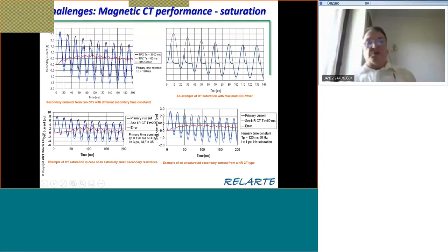And the guy who is developing a relay there, which is installed, for example, even a few hundred meters away from here, and they get such signals from the merging unit as sampled values, so they don't know this. So what will happen? Maybe again the relay will operate for CT saturation inside of either the relay or the merging unit. So we have to consider all of this as a possibility which can happen also in the future.